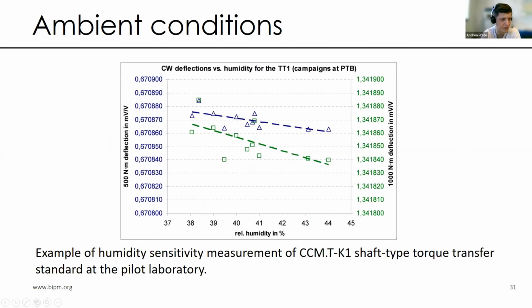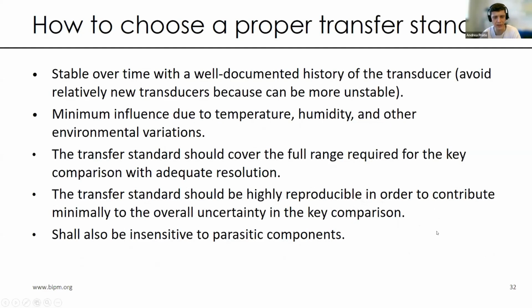Here we can see also another example for a torque comparison, key 1, where a shaft type torque transfer standard was used, and these are the measurements performed by the pilot laboratory, and we can see a very strong dependency of deflections as a function of relative humidity, as mentioned before, especially for shaft type transducers. And in this way, sensitivity coefficients can be used to correct comparison measurements.